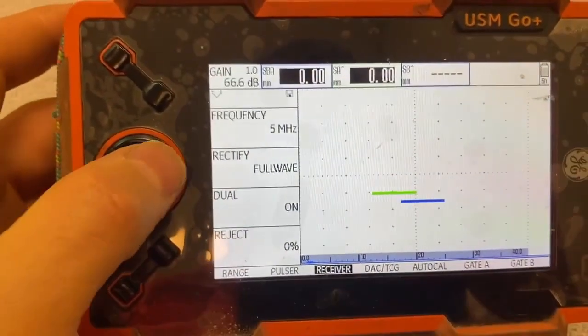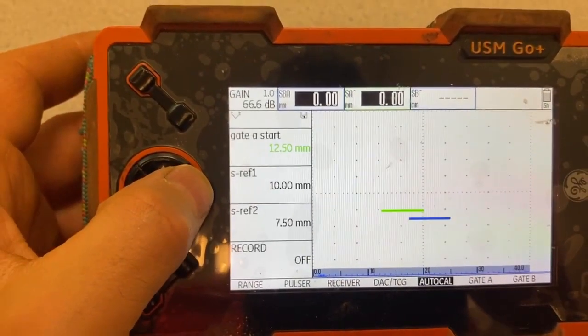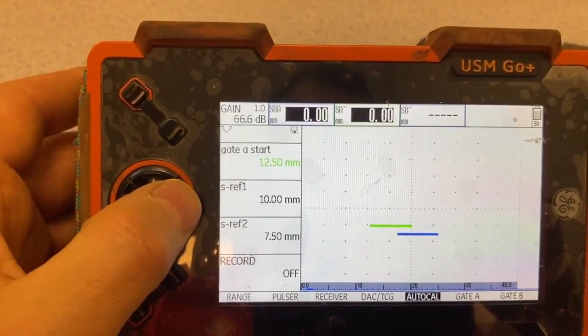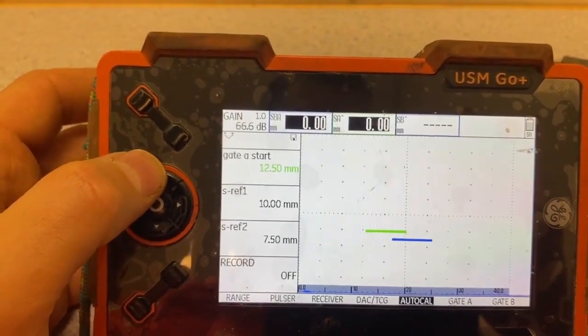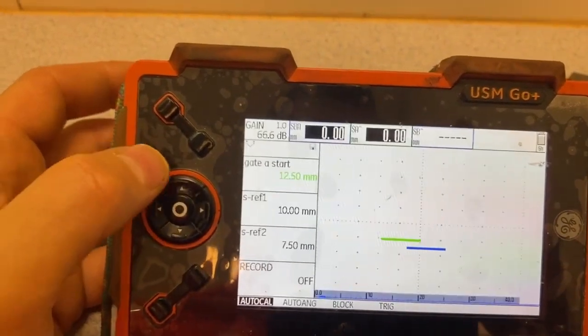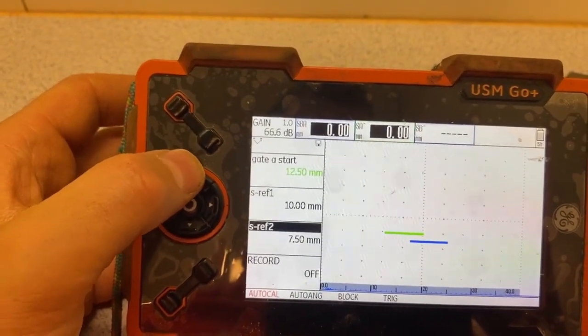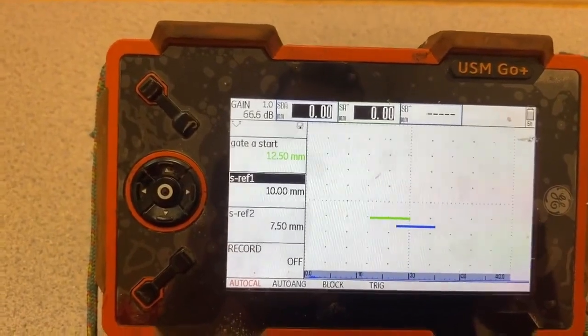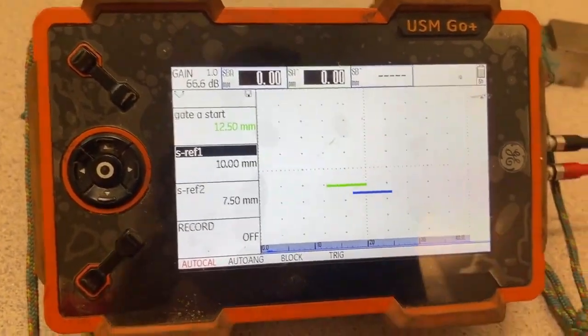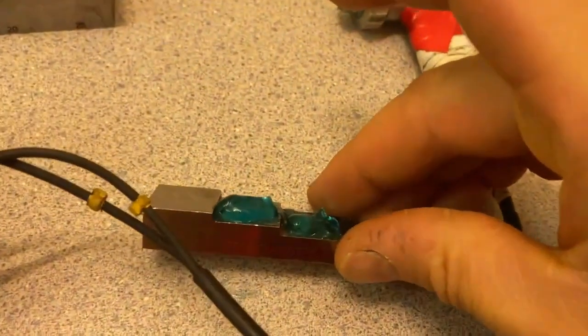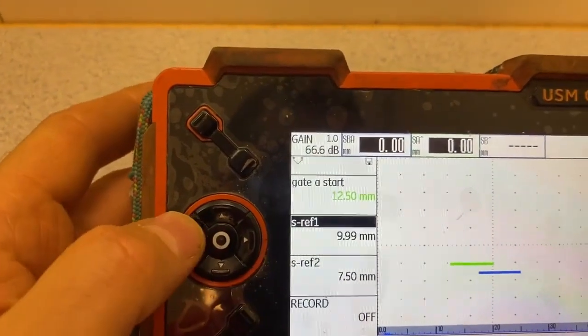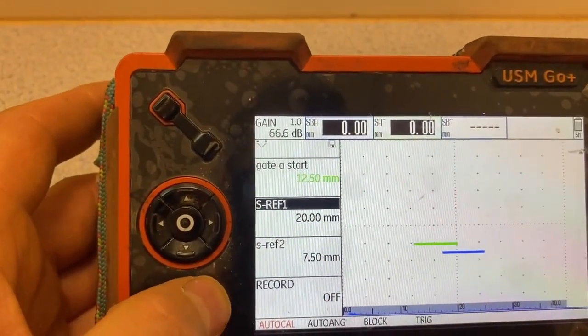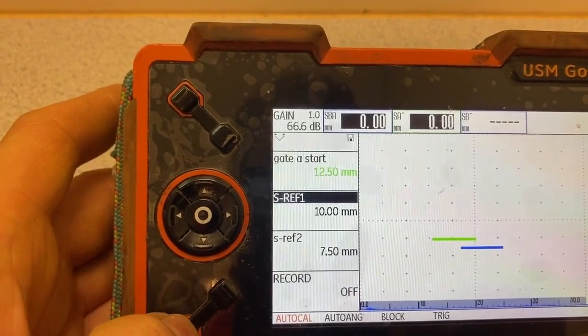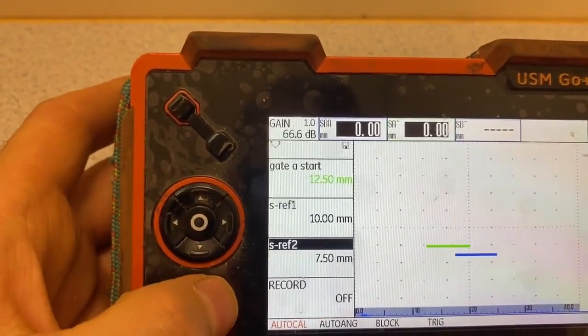Okay, next step, we leave like that, autocal. We're going to use autocal to calibrate it. What we need to do, we go up and we position reference number 1 at 10 millimeters and reference number 2 at 7.5 millimeters. This is because it is 10 millimeters and 7.5 millimeters. We can always change here. Now the first signal will be calibrated on 10 and the second signal calibrated on 7.5.